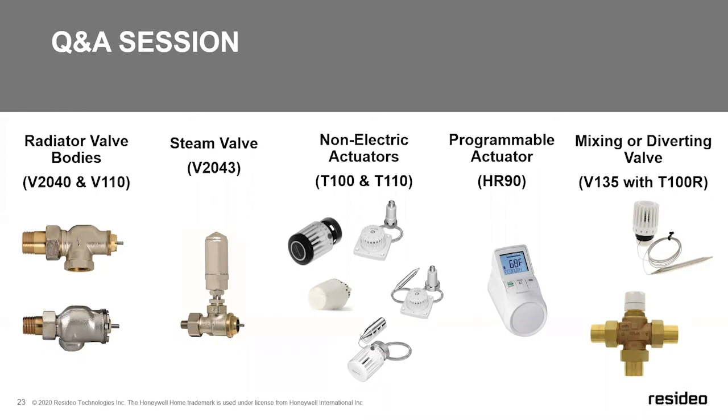What most of the industry is used to, at least in North America, it's a little different in Europe, is digital thermostats: the thermostat calls for heat, it opens a valve, and then by way of an end switch, we tell that valve to tell our pumps and boiler to come on. When you're looking at the non-electric actuators, thermostatic or electronic or even manual, there's nothing there that goes back to the boiler. As I showed on the slide after the question came in, there's nothing there to tell it to come on.